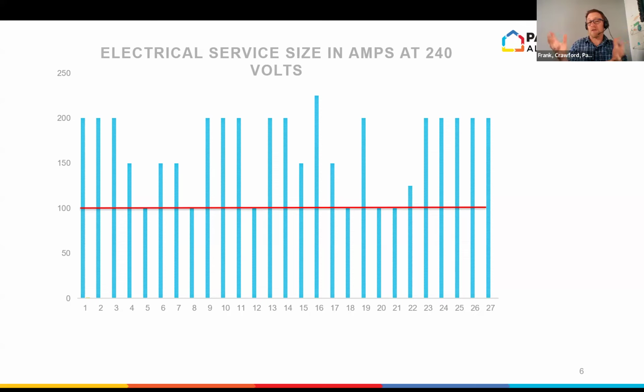And so the next question was, was that a problem? Could they have stayed on a 100 amp service? Because we want to stay on a 100 amp service because that's what the grid is already used to providing. And if we can maintain that, then the impact to the grid is going to be reduced. So this graph just shows the red line is a 100 amp service, each one of our 30 or 27 homes, and what their electrical service to the building was.